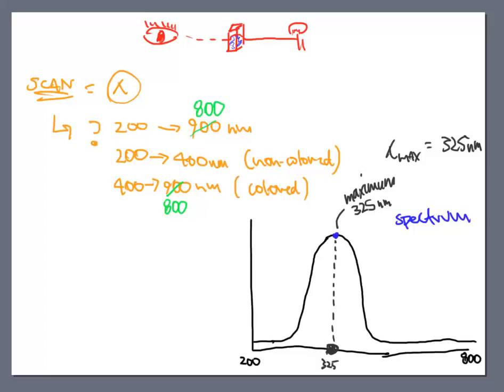So in the last video, we talked about the purpose of a scan. And a scan is to make our job easy, right? No one says that working in a laboratory has to be difficult or has to be hard. So the purpose of the scan was for me to go in and take a sample and put it into the instrument, close the door of the instrument, and give it a window to look for. I can make the window as large or as small as I want.